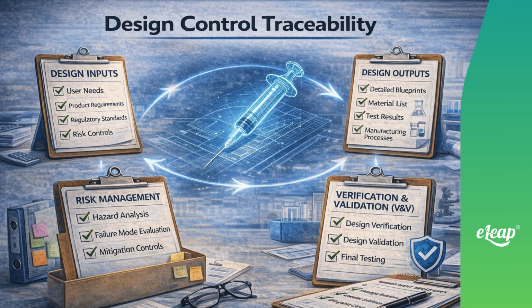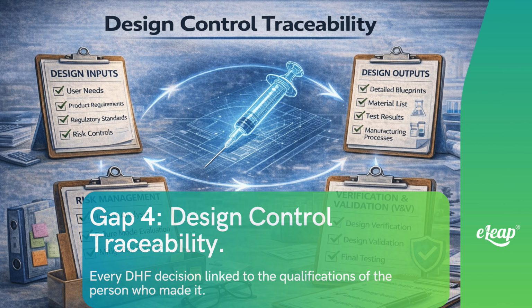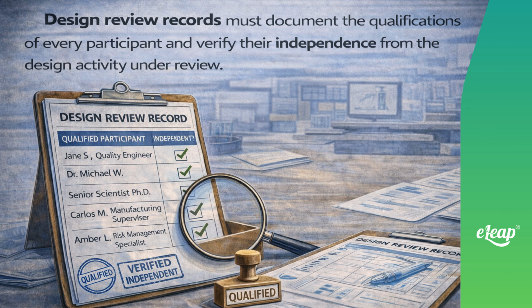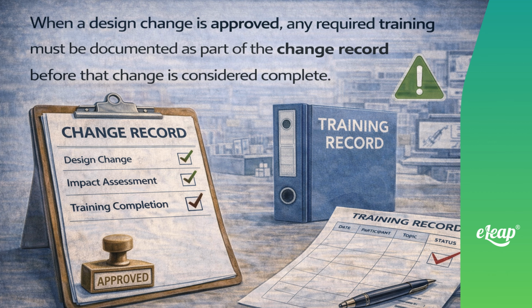Design control traceability. Design review records must document the qualifications of every participant and verify their independence from the design activity under review. Personnel conducting specialist activities, risk management, software development, human factors, biocompatibility, must have training records tied to the specific standards governing those activities. And when a design change is approved, any required training must be documented as part of the change record before that change is considered complete.